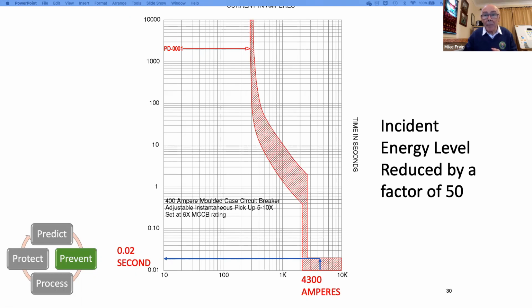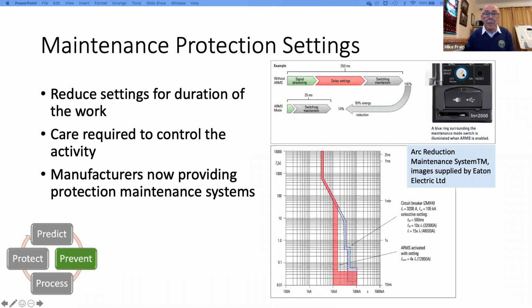So that's very common. Clearly, we can use it only for permanent situations where it's safe to do so, where it doesn't have a problem with discrimination or interfere with the load that's on that particular equipment. On the same vein, sometimes it's not possible to alter upstream settings on a permanent basis because of protection coordination issues, but interactions with energized equipment of any description will inevitably lead to some sort of risk. A solution might be to temporarily alter the instantaneous settings on circuit breakers for the duration of the work and then put them back again. But this in itself does require carefully thought out processes to ensure that maintenance settings are not left behind after the work is completed.